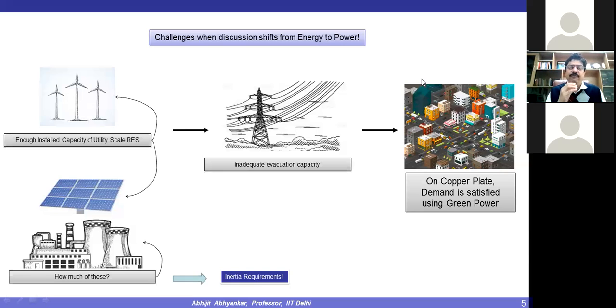For conventional fossil fuel based thermal generators, the rotating masses store kinetic energy. Whenever there are changes in the balance between load and generation, this balance is compensated through the kinetic energy stored in the rotating masses. This, in simple terms, is called the inertia requirement.